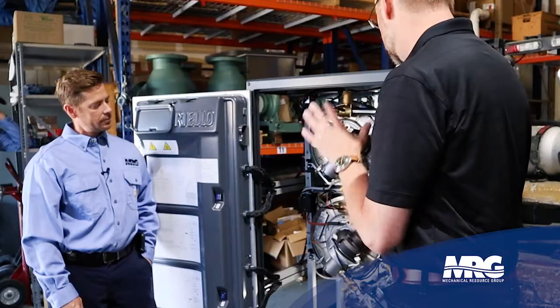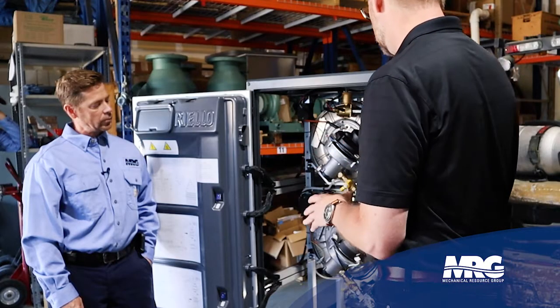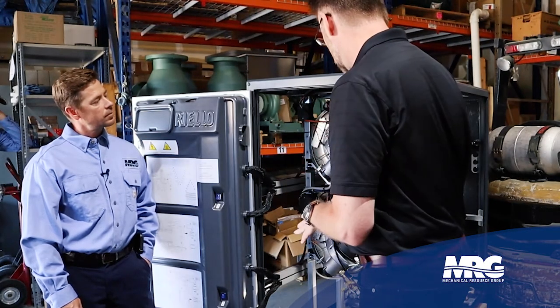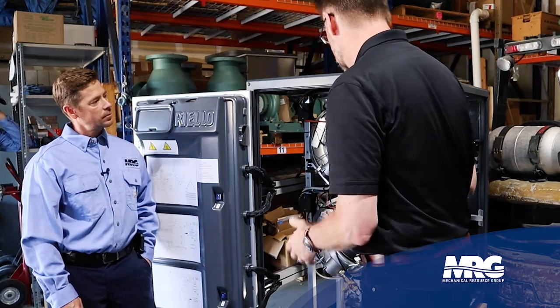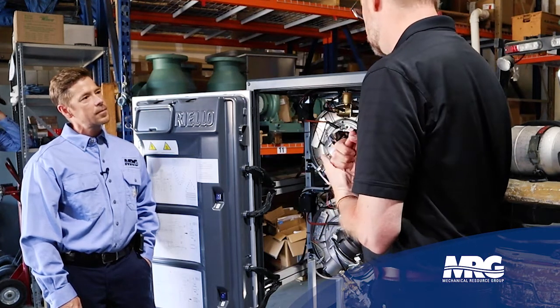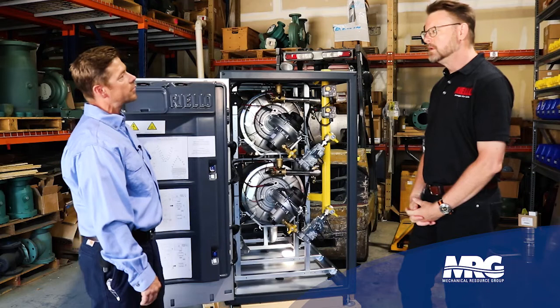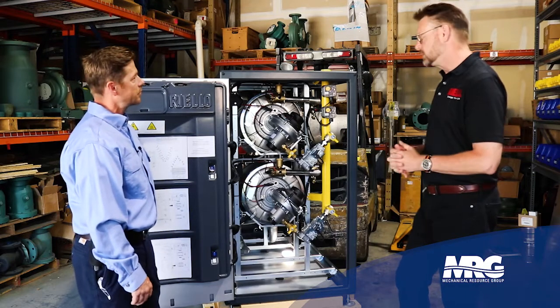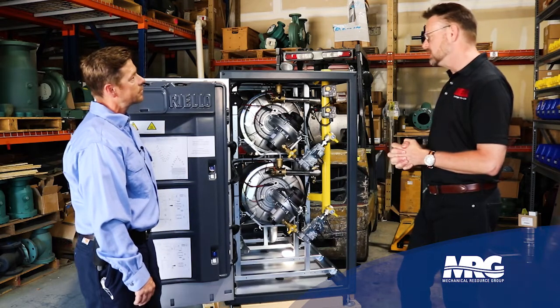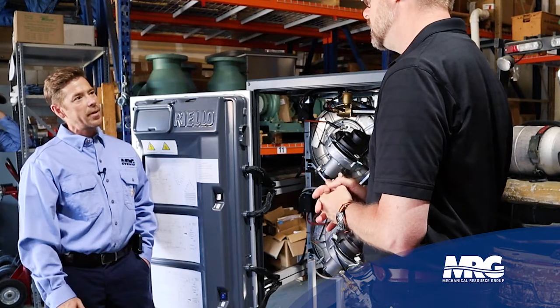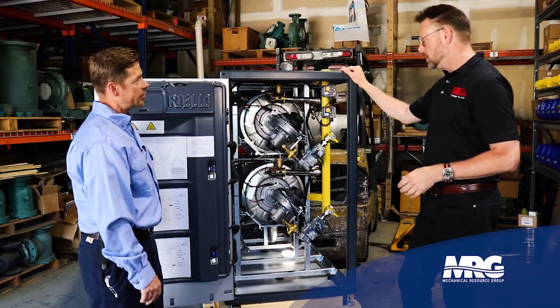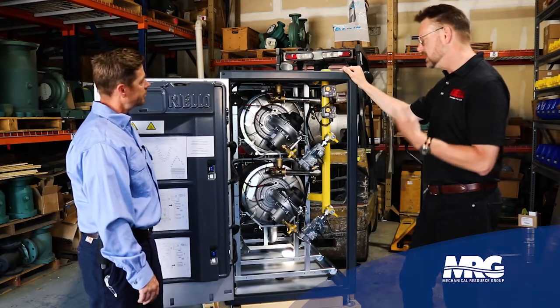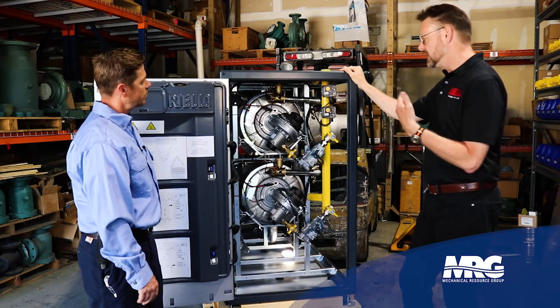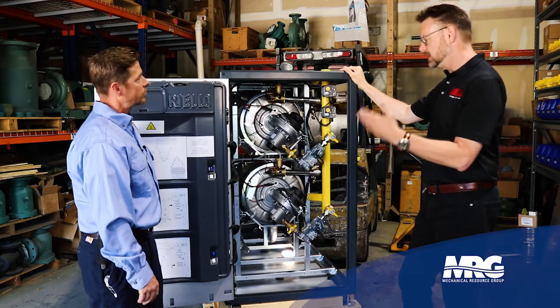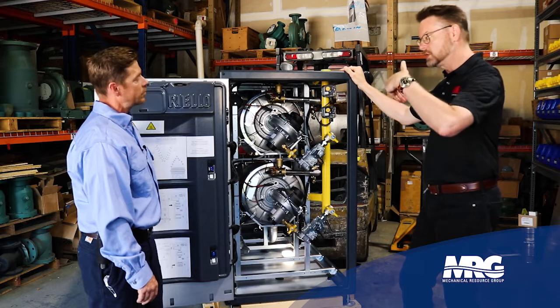Oh yeah. Okay, so that's one situation, an ignition problem that we threw here at the array, and we would have continued operation. Is there another problem that you've dealt with recently? Water flow issues. Water flow issues, okay, and how did that manifest with the unit? Basically, the paddle switch wasn't making, to indicate that water was there. Okay, so you had a fired heat exchanger, a boiler, that was having flow issues, and it was being indicated because the flow switch was not making.